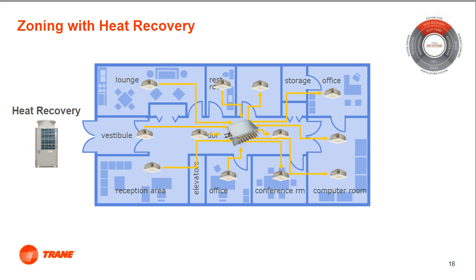Zoning with heat recovery systems is straightforward, with some exceptions, because the loss of comfort control is mitigated with the simultaneous heating and cooling capability. When the system is in a simultaneous operating mode, some of the zones can be heating and returning liquid, while others use liquid for cooling. The outdoor unit is providing either net heating or net cooling capacity, depending on the individual zone loads. Using heat recovery may enable fewer systems to be used on a building and actually save first cost, all while improving comfort.